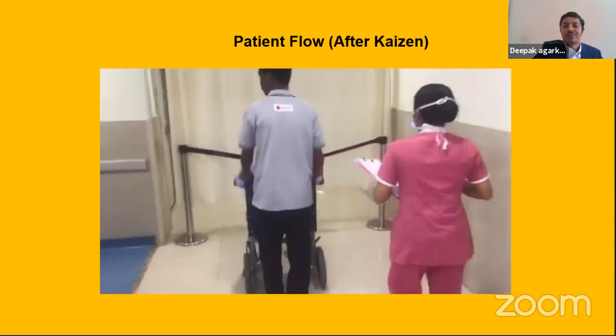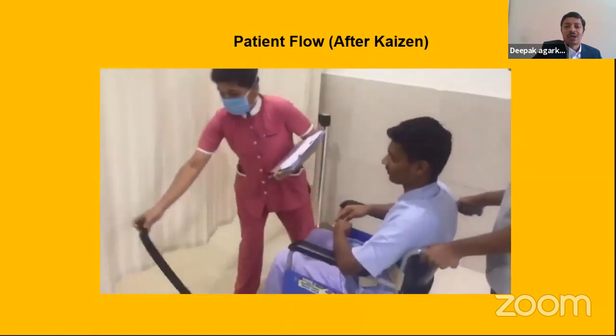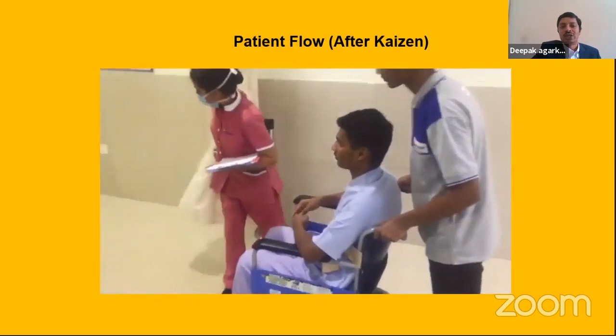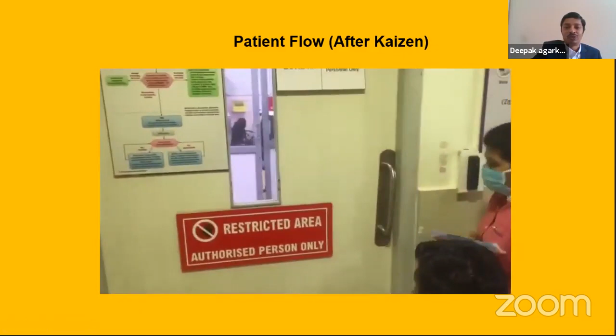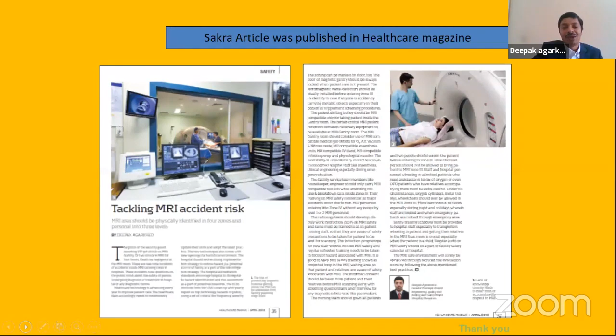From there, the patient goes to the MRI area through a common corridor. You can see here the zone 2, and you have the signage for a restricted area. Now the nurse guides the patient to the MRI zone 3 area, wherein again you can see access control. She first presses the nurse call so that the technician will come, and then she can use the access control, and a technician comes and the patient is taken to zone 3. Of course, zone 4 I have not shown, because zone 4 is where the gantry, where the MRI exists, where the scanning happens.